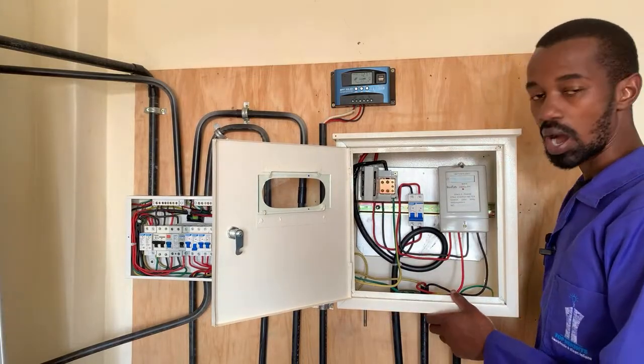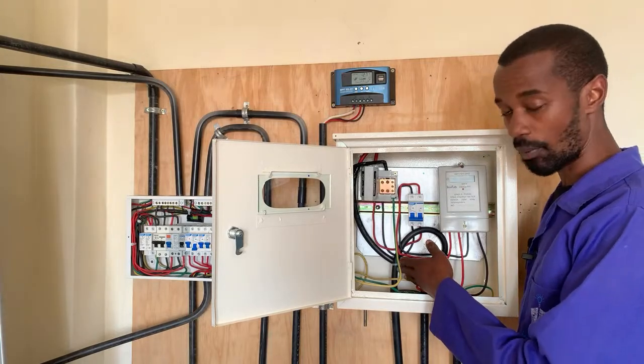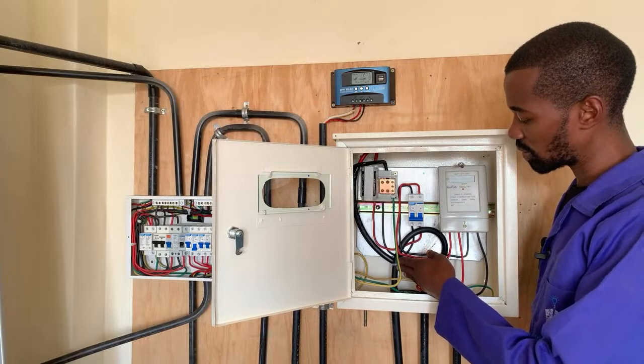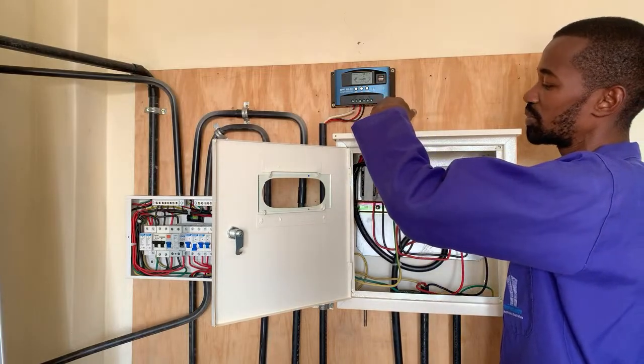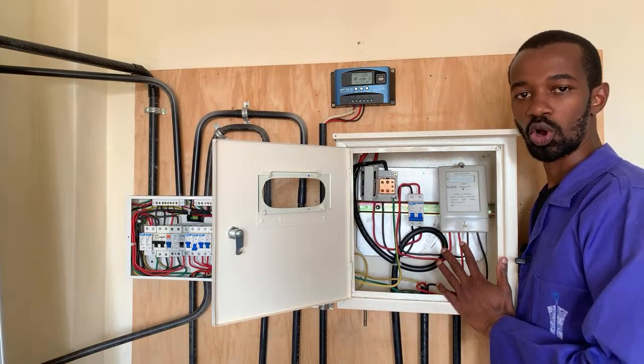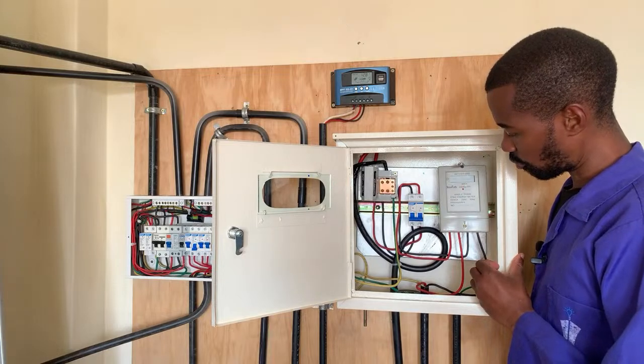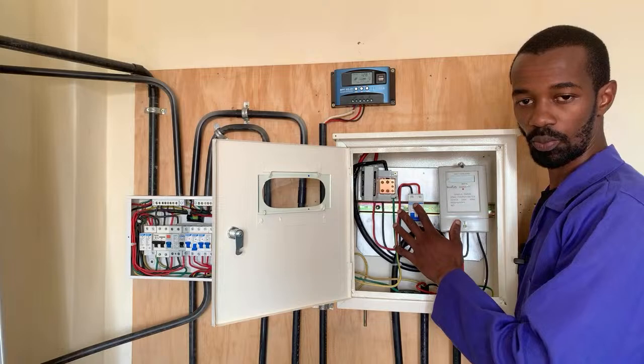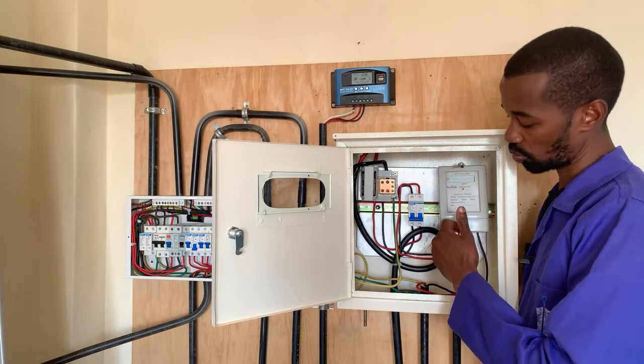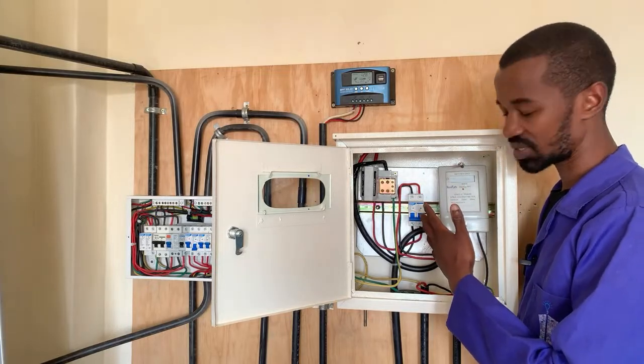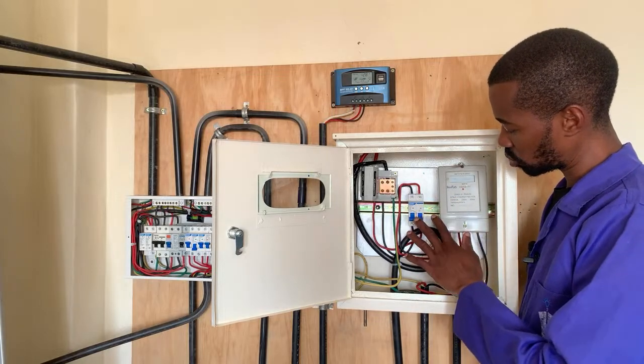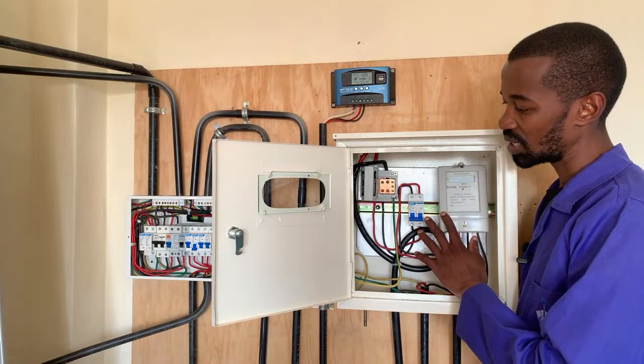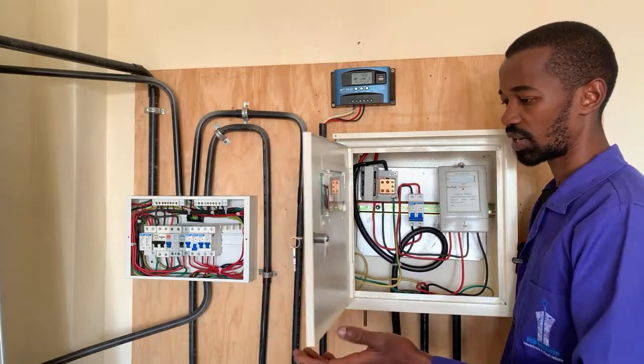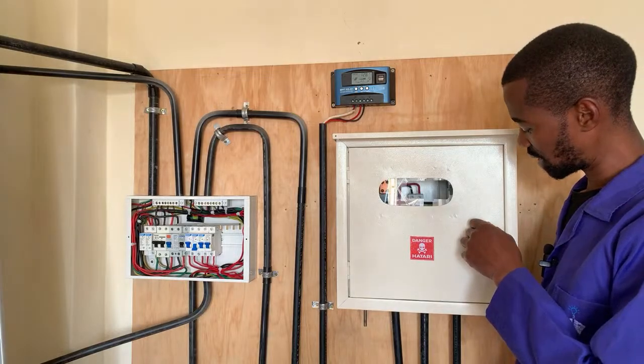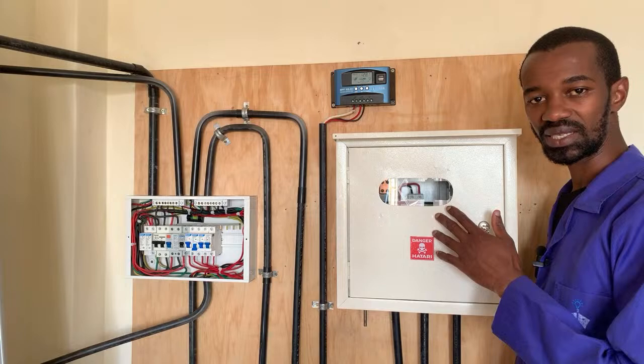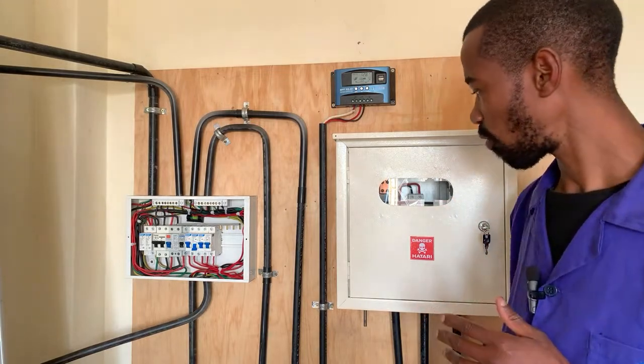In our previous live session, we said it's important to have power coming from below because of issues with rainwater. If you have inlets from this part here, the meter box will be susceptible to rainwater or moisture coming in and affecting the components. The rainwater may cause the components to rust, or it may short circuit the phase and the neutral. So water is an enemy to this setup, or water is alien to these electrical fixtures. The meter box must be kept as dry as possible, and that is one area where you might encounter challenges if there is an issue with water.